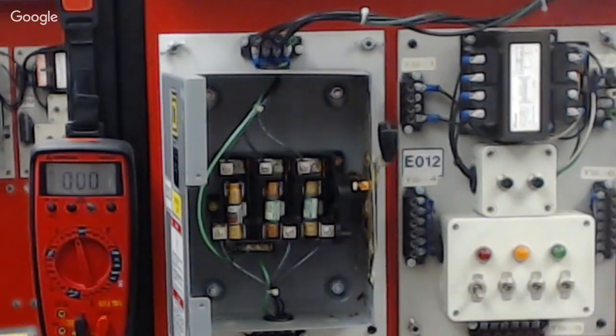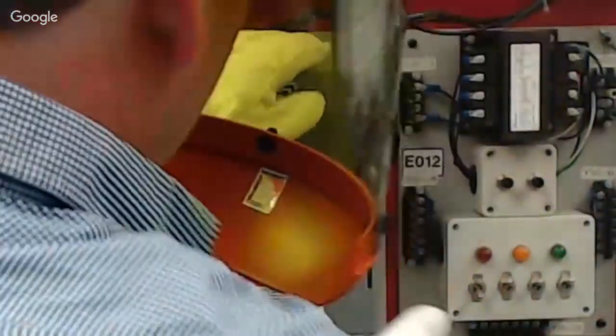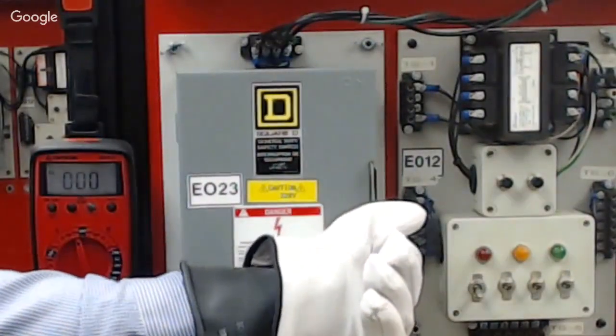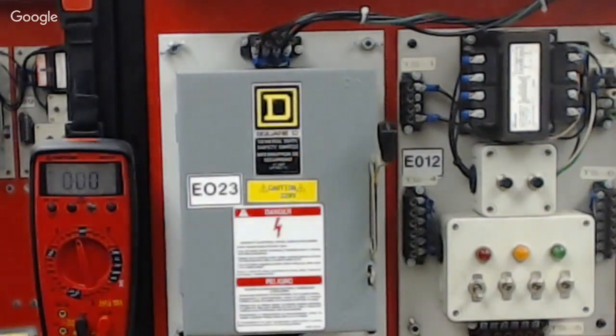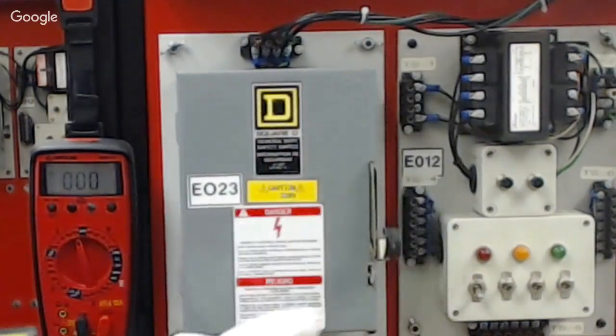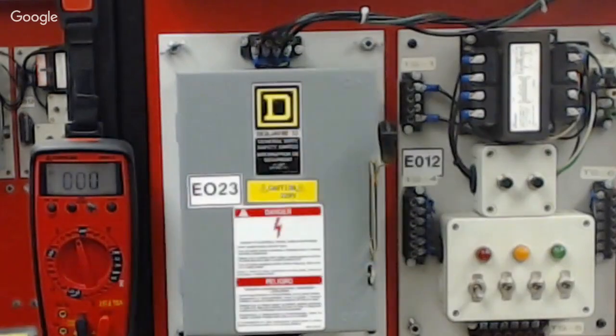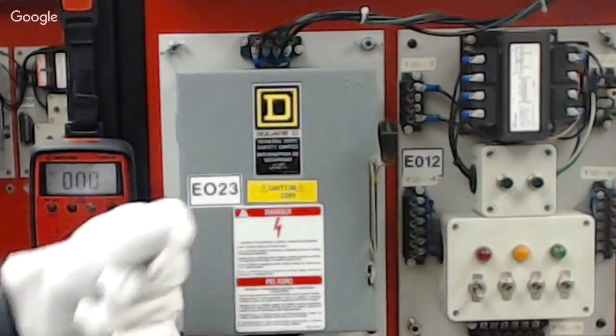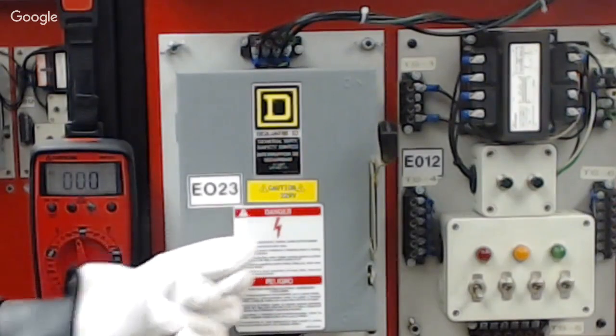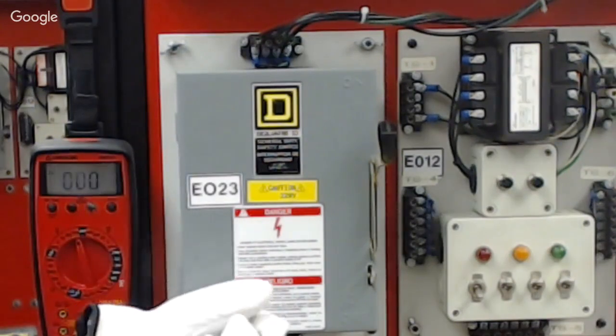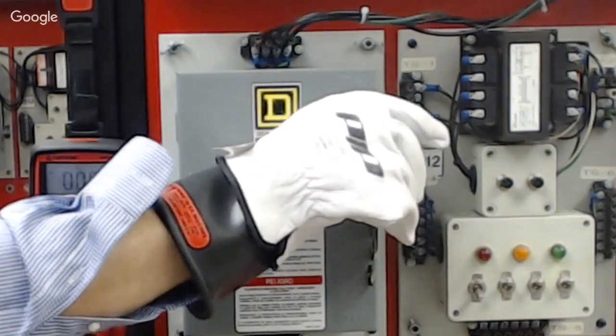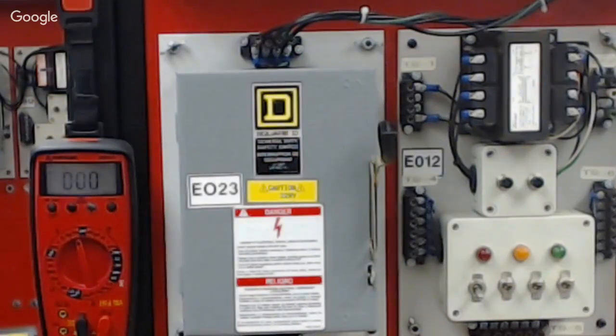So remember, when we turn these off, we should not be facing these. We should be standing out of the way. There's another video where we apply a lockout, but remember, don't stand in front of these when you turn them on. If they do have a load on them, there could be an arc flash. Right now we have a system with nothing on it. There's not going to be an arc flash. And if we stand in front of these, they can become projectiles. So the proper way is to stand facing it, off to the side, and turn the disconnect on to make sure the sparks don't blow back under your helmet.